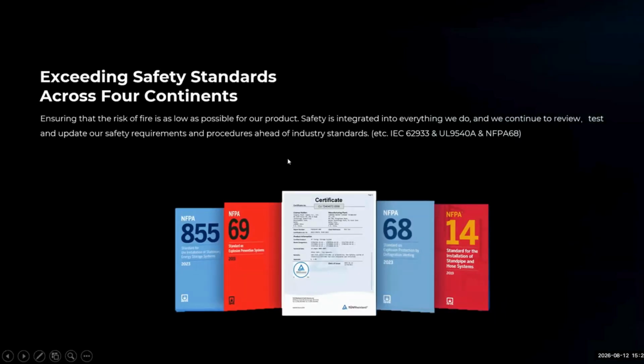For all the safety design, we have certificates. For the explosion venting panel, we got NFPA 68. For thermal runaway, for the modular design and rack design, we got certificates for UL 9540A. For the internal circuit of the battery module, we follow IEC for this product, so we also got IEC 62933 for the internal safety design.